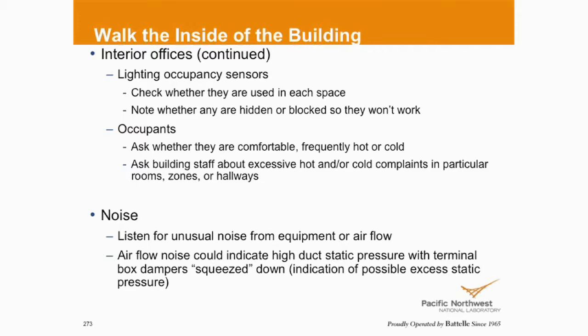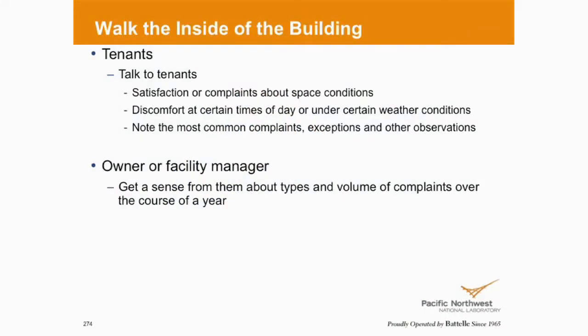Unusual noises. Do we hear, because we've got high static pressure and the dampers are squeezed down, a whistling noise coming out of the diffuser? That could be indicative of excess static pressure. If we've got rooftop units, we might hear belts, noise, or even air handling units that transmits down the ductwork. Again, talking to the occupants, finding out when they're comfortable, when they're not. Can we connect the dots to what's going on, either with equipment, with the controls, or both?